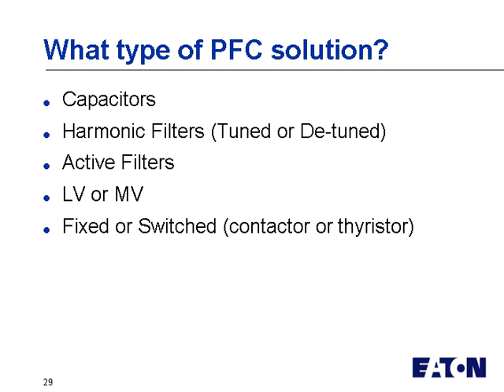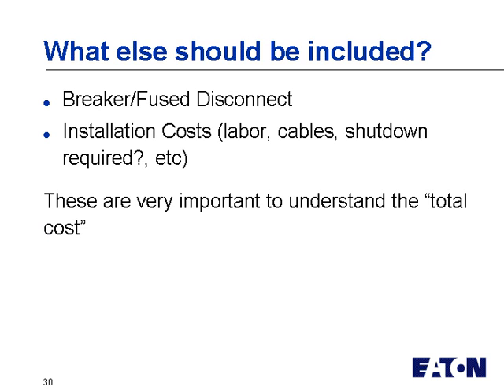Now, what type of power factor correction equipment should be selected? Well, what's available? Well, capacitors are the easiest or most fundamental power factor correction solution. And then there's harmonic filters, which we typically call tuned or detuned. And then there's things like active harmonic filters or active filters, which actually are power electronic equipment, a lot like a variable frequency drive, if you're familiar with those, that provide power factor correction. And then you have to consider, really, again, low voltage or medium voltage, fixed or switched. What kind of power factor correction solution do I need to apply?